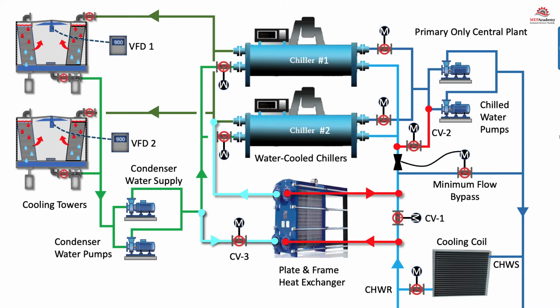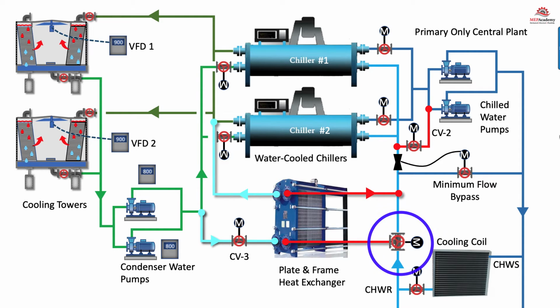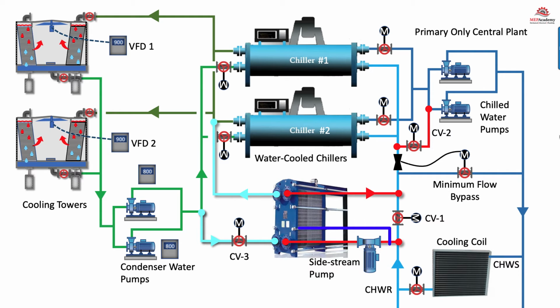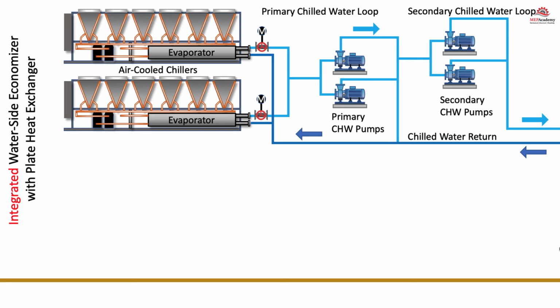There's the option to use a 3-way control valve instead of a 2-way valve, or an option to use a side stream pump to pull the chilled water return through the heat exchanger. Adding a waterside economizer to an existing air-cooled system: you can retrofit an existing air-cooled chilled water plant with a waterside economizer as we show here.